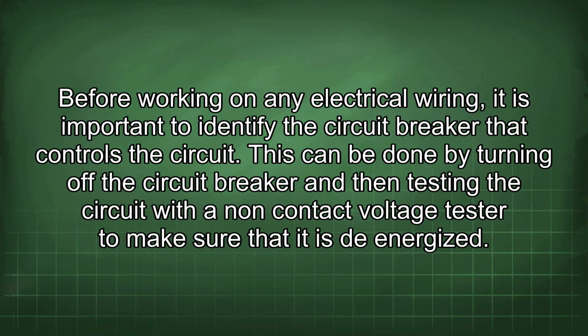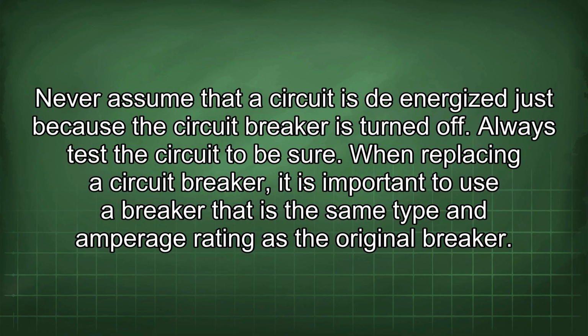Before working on any electrical wiring, it is important to identify the circuit breaker that controls the circuit. This can be done by turning off the circuit breaker and then testing the circuit with a non-contact voltage tester to make sure that it is de-energized. Never assume that a circuit is de-energized just because the circuit breaker is turned off. Always test the circuit to be sure.